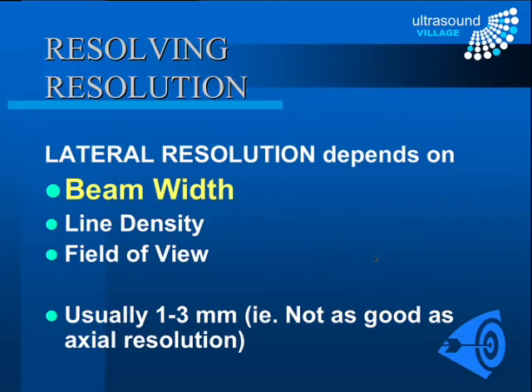For lateral resolution — resolution perpendicular to the direction of the beam — the primary determinant is beam width. Other factors include line density and field of view. In general, lateral resolution is one to three millimetres on most current machines, which means it is not as good as axial resolution. That is important if you are trying to do very precise measurements, though for most clinical purposes we don't need to be quite that accurate.